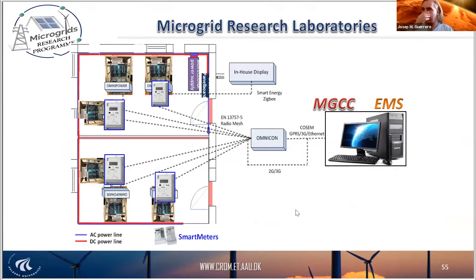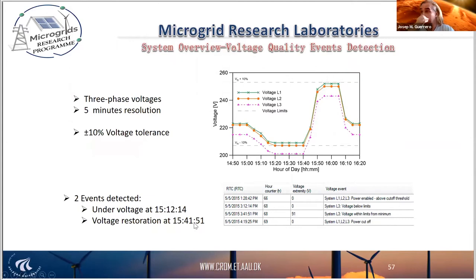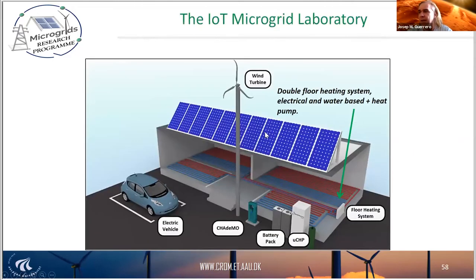When we have a number of smart meters, for instance in Denmark, we can take up to 500 houses, collect information for the utility, and present power quality information. The important thing is that not only the utility can access it, but you can also get it from home using your own signal through an optic eye plugged to a laptop via USB. These are real measurements from a three-phase system — here in our houses we have three-phase — and you can see one of these phases is unbalanced. Depending on the hour, there is some under-voltage or over-voltage, so we can know if we are inside the limits. This is amazing, especially now that we can see more electric vehicles plugging into the system.